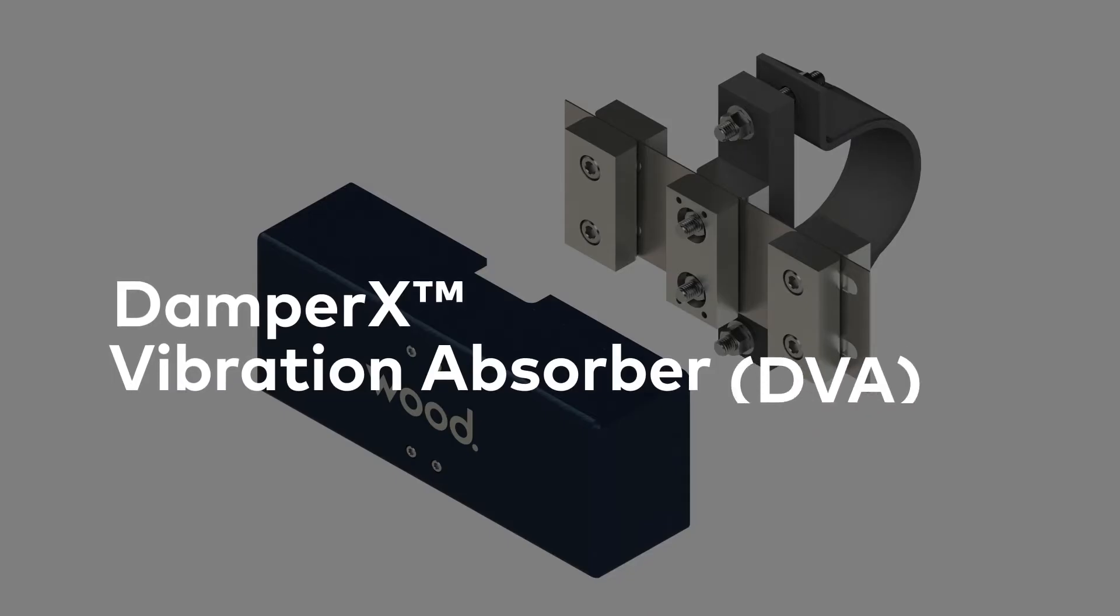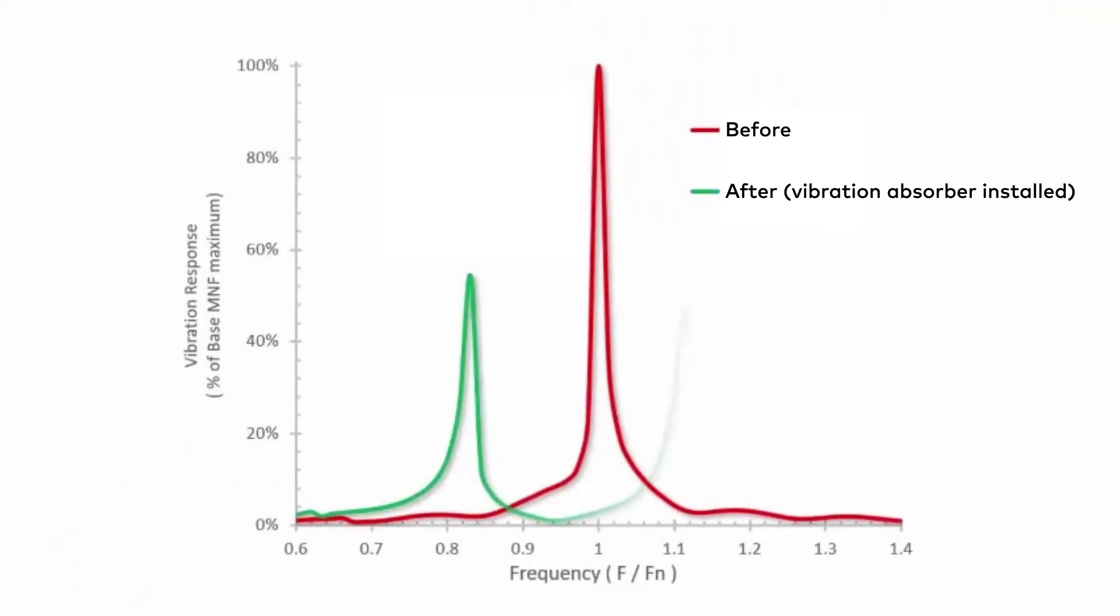Wood's DamperX vibration absorber is just such a device. Our standard DVA typically produces 40 to 50 percent reduction in vibration off base levels, and for a good many of the piping and vessel vibration problems we see, that's all that's needed.